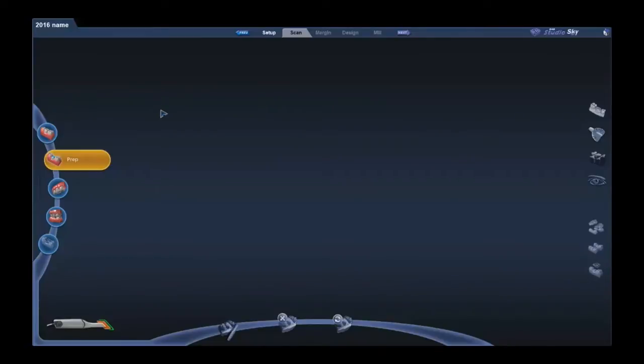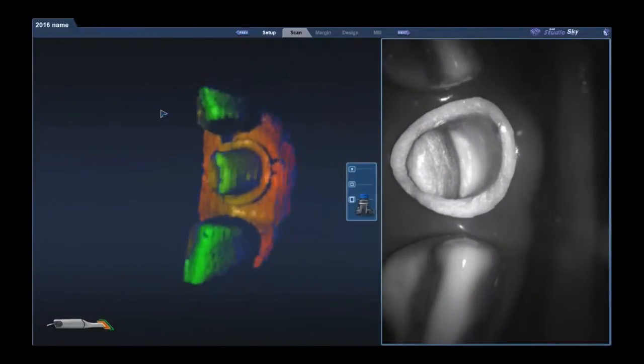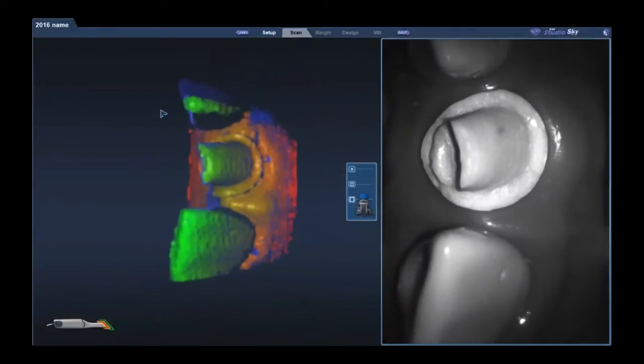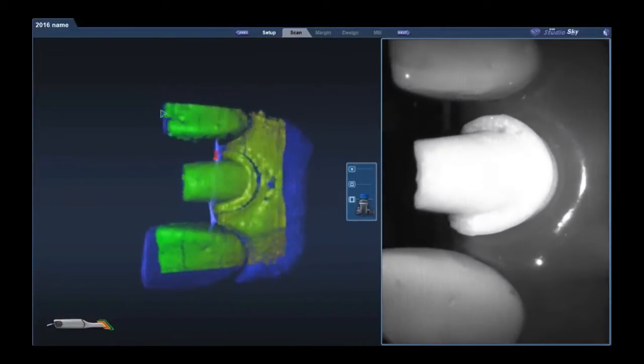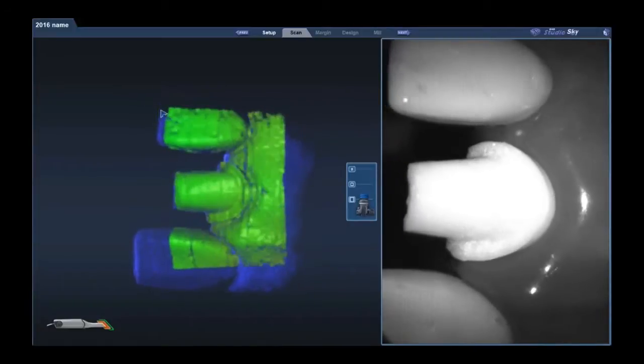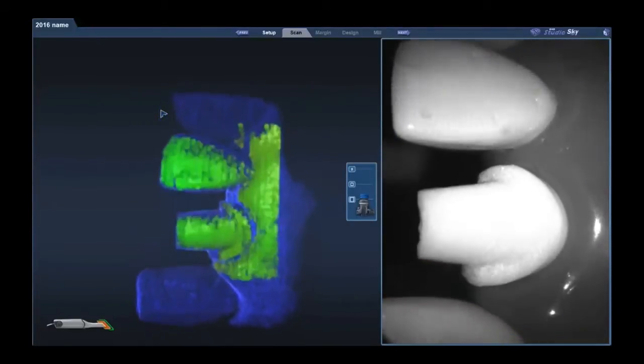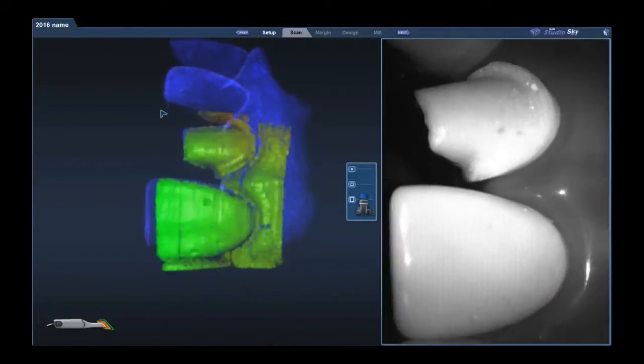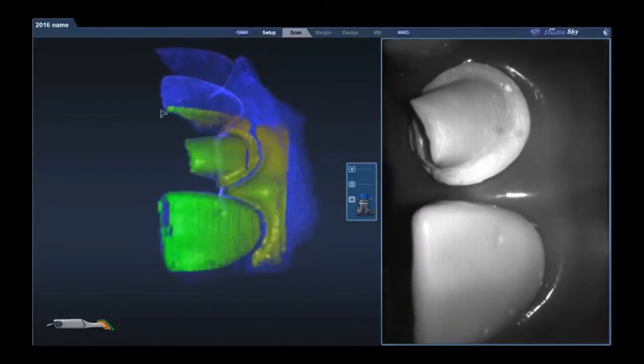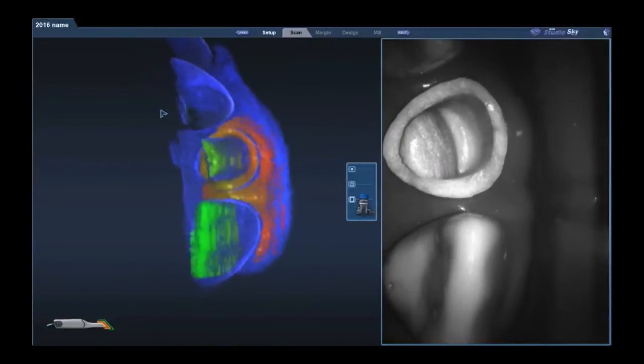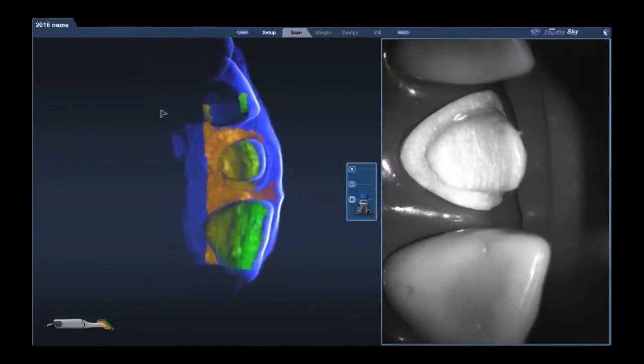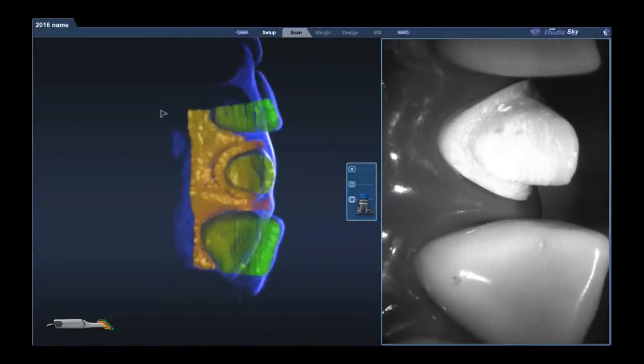And there's multiple tabs that they could scan under, but you want to make sure that they're scanning under the prep tab, and they're going to activate the camera and start doing imaging, and you'll notice that it's a video speed capture, powder-free imaging that's rotational-based, so you're truly capturing all the information. And the green color is giving visual feedback, and green represents a really good focal depth, and the oranges and the reds are still good data being captured, so it's just meaning that you're getting a little bit farther away.